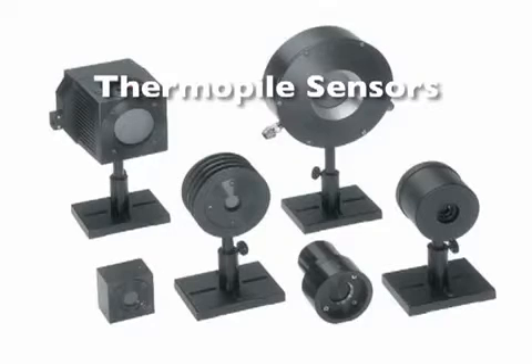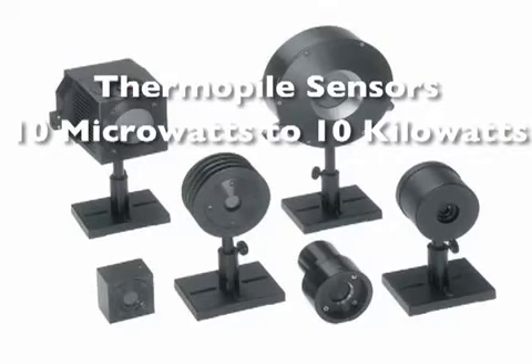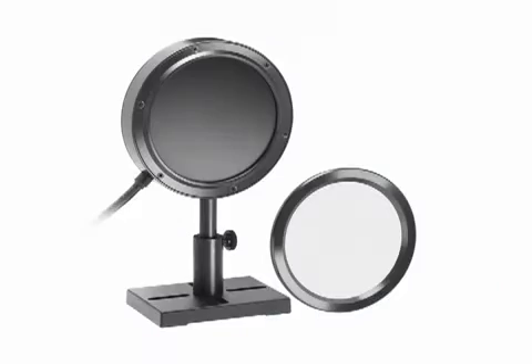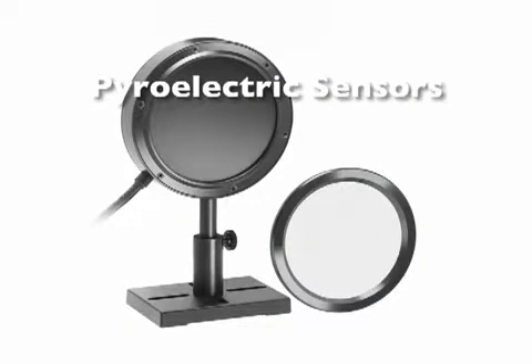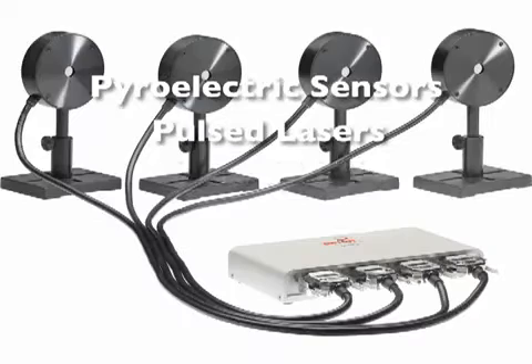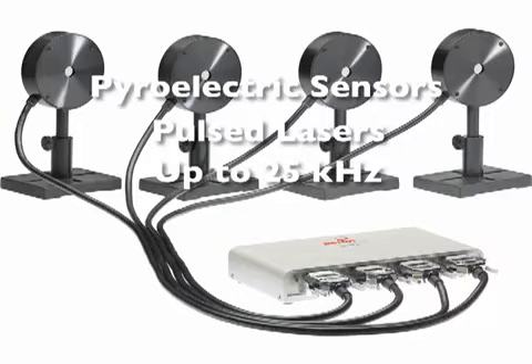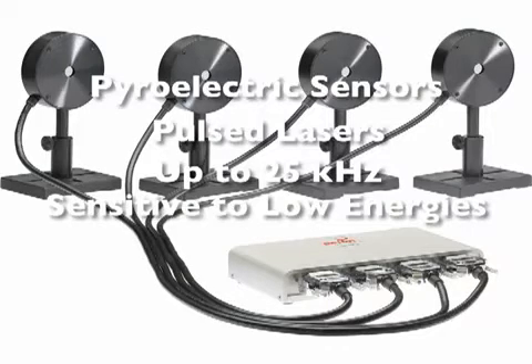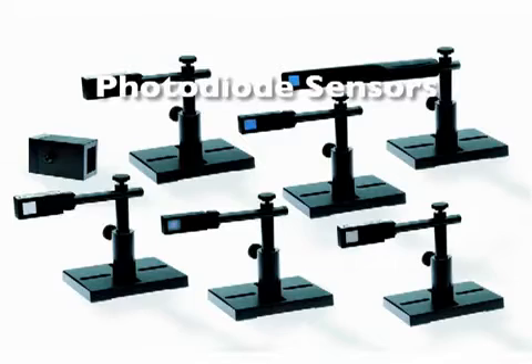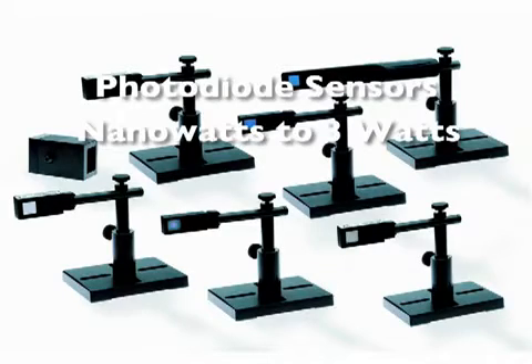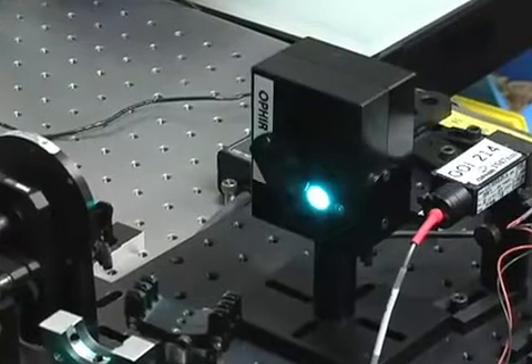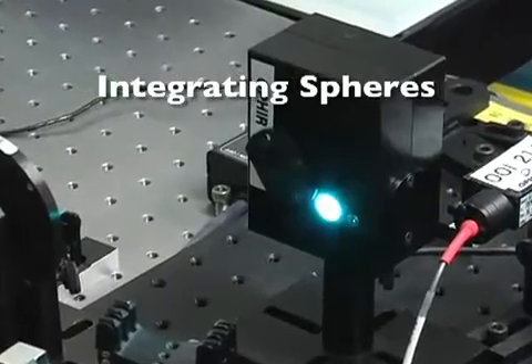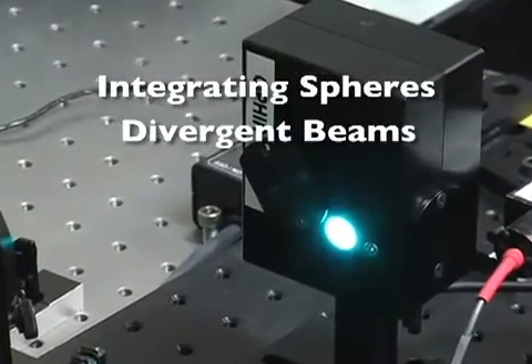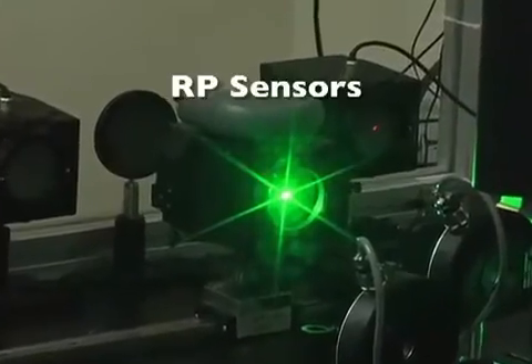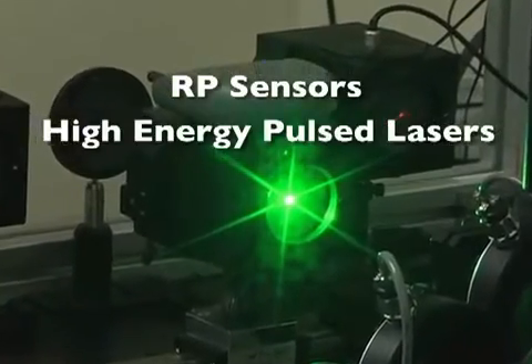Thermopile sensors measure tens of microwatts to 10 kilowatts. Pyroelectric sensors measure the energy of repetitively pulsed lasers at up to 25 kilohertz and are sensitive to low energies. Photodiode sensors measure fractions of a nanowatt to about 3 watts. Integrating sphere sensors measure diode lasers with divergent beams. RP sensors measure high-energy repetitively pulsed lasers.